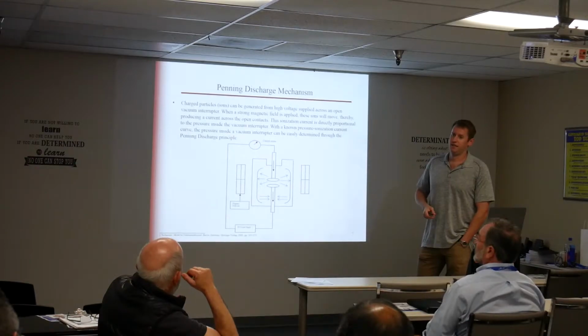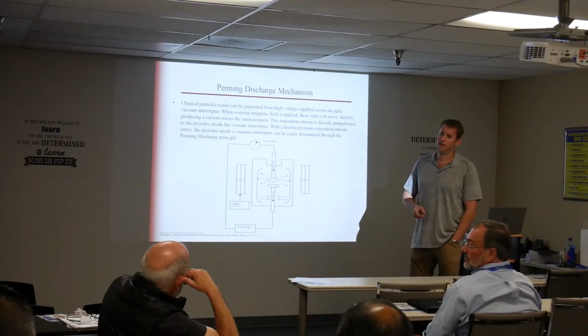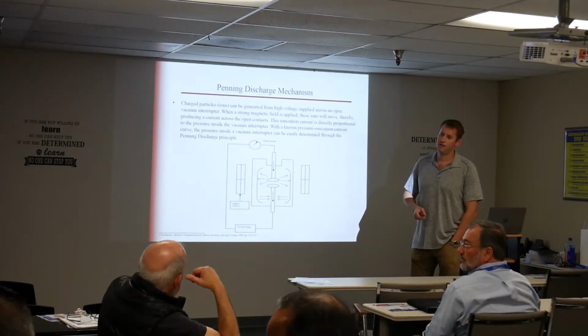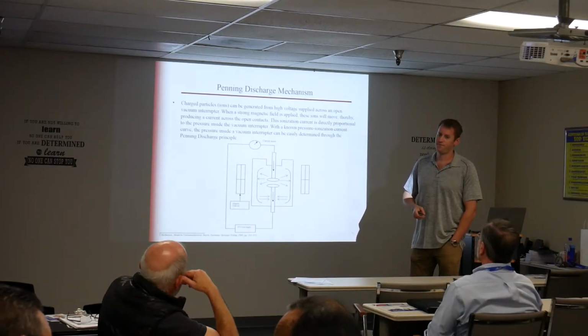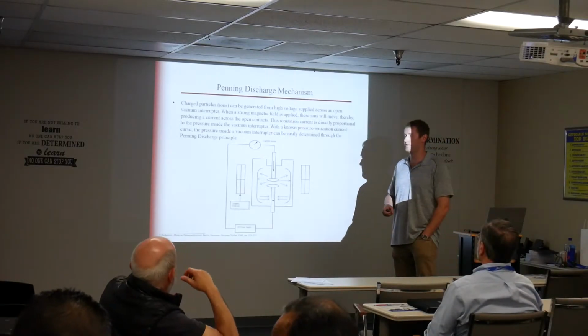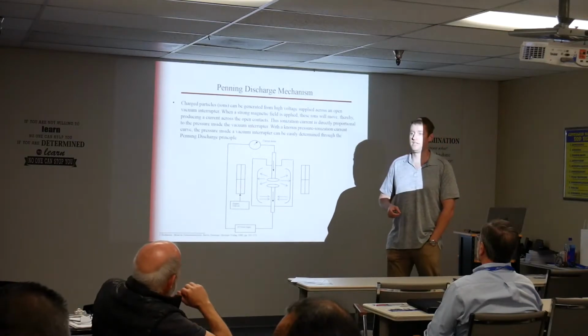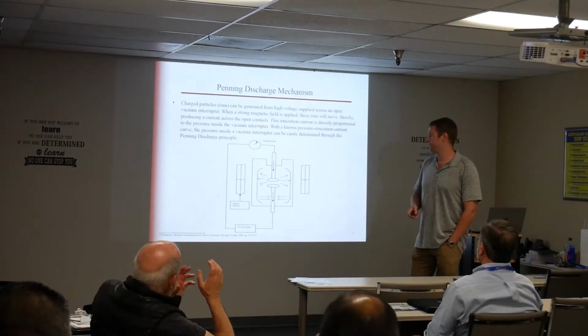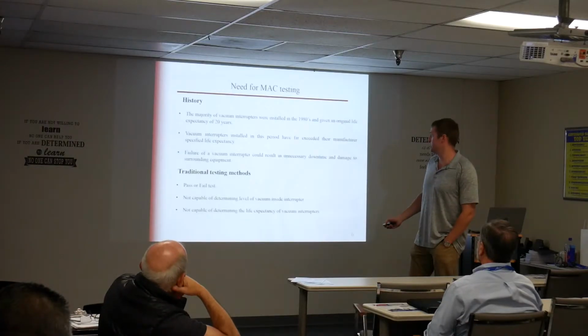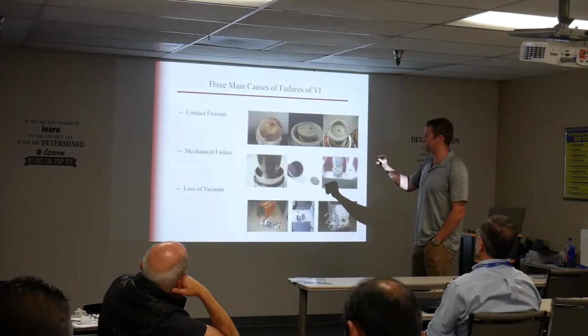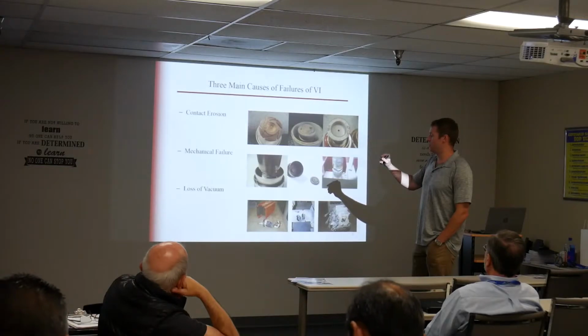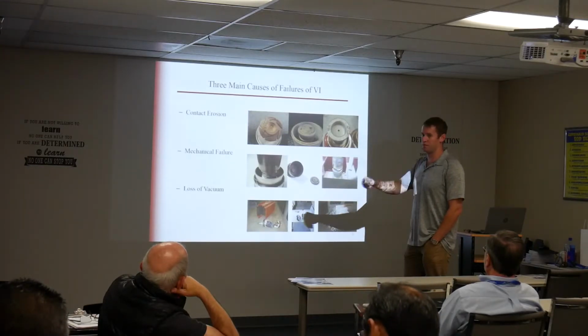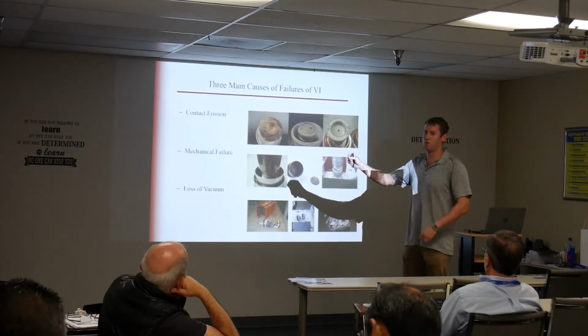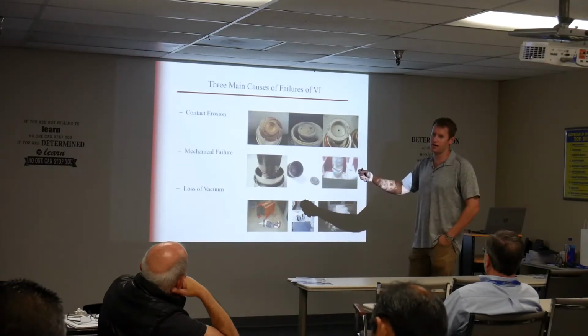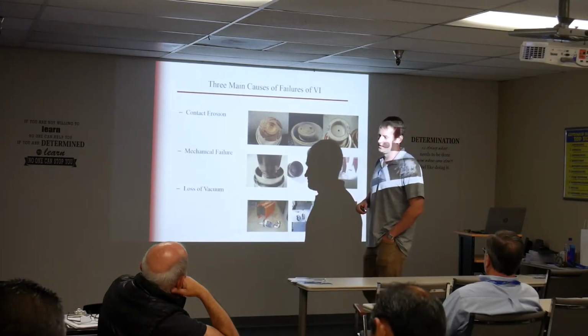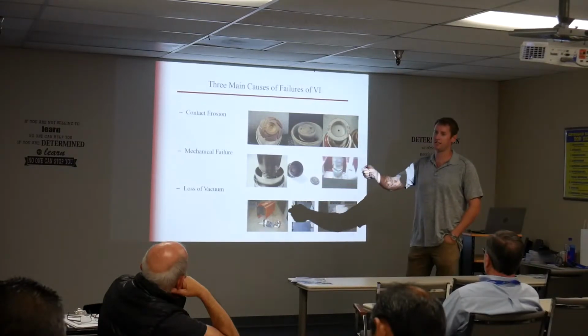I would imagine the worst case failure on those things is catastrophic failure when they explode. Yeah, if it's called upon to interrupt a fault whenever the bottle's bad. And then you have molten metal and the glass. And the other thing is, like I said, it has that tiny contact gap. So if the bottle's bad, you open the breaker, the breaker says it's open, but one phase is bad, it's still carrying current, unless you go out there with one of those non-contact voltage detectors and check each phase.